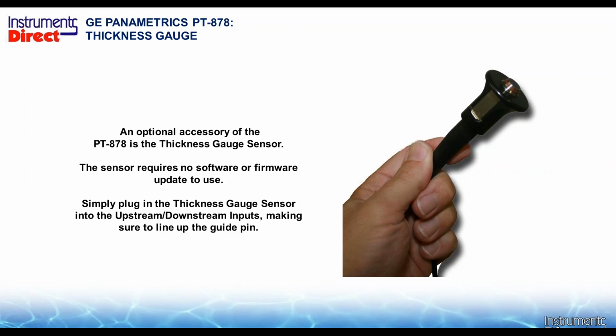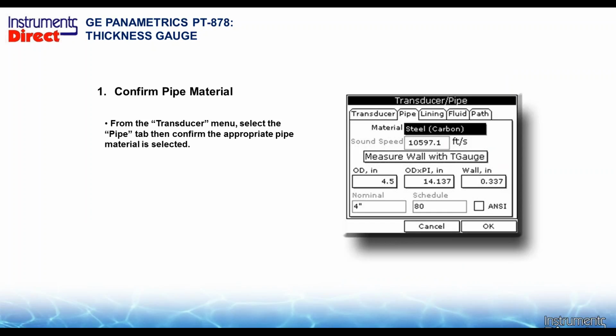So in most cases, the ANSI pipe chart book is more than enough to measure your pipe. The thickness gauge is very helpful in applications with older pipe where there's wear inside the pipe. And it's great for monitoring stressed pipe and pipes that do need some service. So very good for that particular application. Less and less popular as a flow meter tool. The ANSI chart usually suffices. But if you have one there, here's the transducer method.